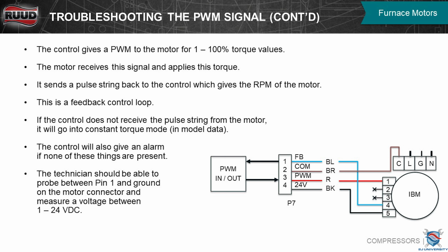So one thing that they have changed a little bit is the blower motor. And this is the new wiring of the blower motor. On the blower motor, you still have CLGN, which is your high voltage coming in. It's done on air handlers, so it's 208, 230 on air handlers, or it'll be 120 volts. You have constant 120 volts. ECM motors have been this way forever. You always have a constant 120.